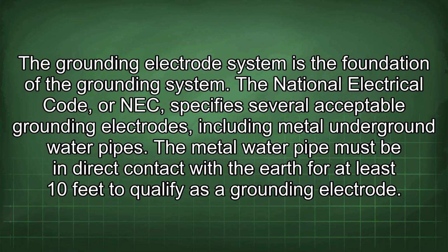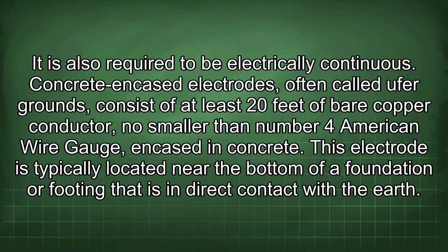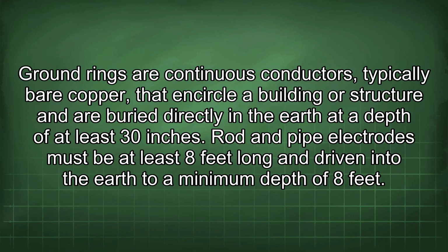The metal water pipe must be in direct contact with the earth for at least 10 feet to qualify as a grounding electrode. It is also required to be electrically continuous. Concrete encased electrodes, often called Ufer grounds, consist of at least 20 feet of bare copper conductor, no smaller than number 4 American wire gauge, encased in concrete. This electrode is typically located near the bottom of a foundation or footing that is in direct contact with the earth. Ground rings are continuous conductors, typically bare copper, that encircle a building or structure and are buried directly in the earth at a depth of at least 30 inches.